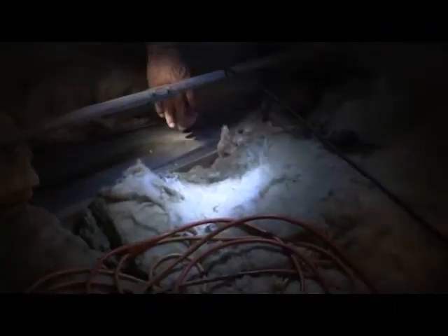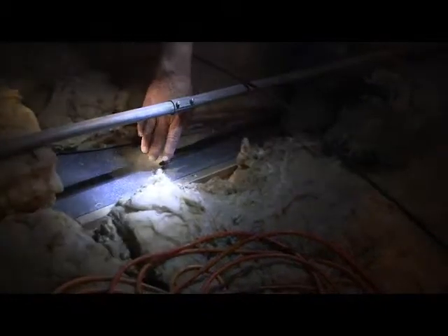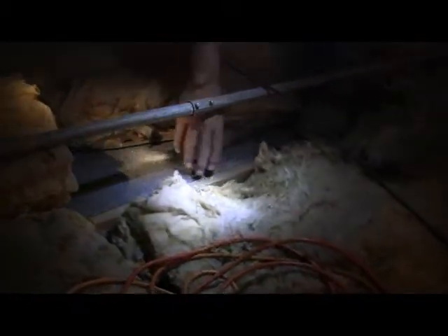And you can look at this panning. This is a metal that's nailed about every 6 inches onto the rafters here. And you can see I'm seeing little wafts of smoke coming up out of these gaps, but all along every one of these, and there's one of these running to every office, there's going to be just generalized leakage of the air into the system from the attic.